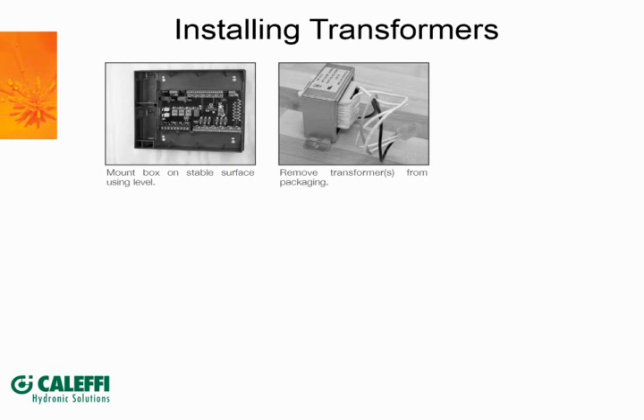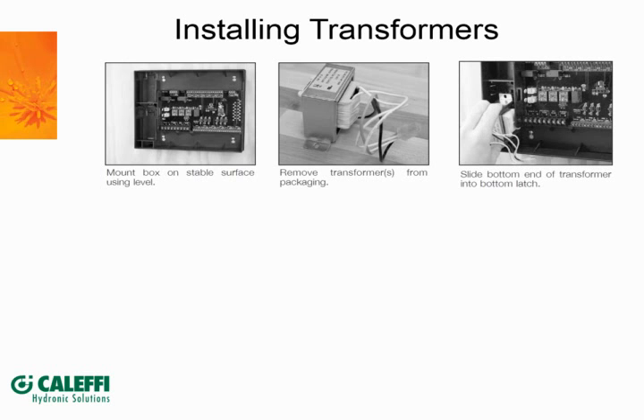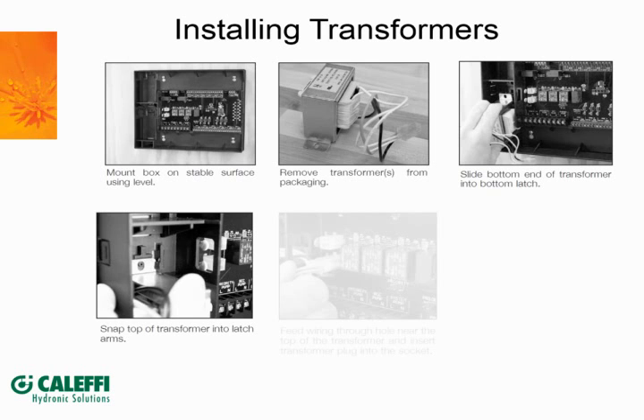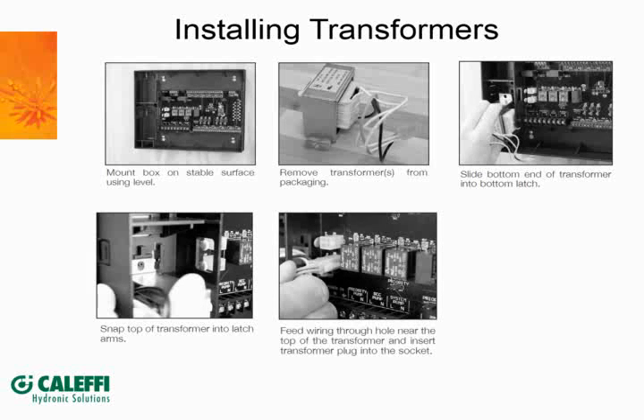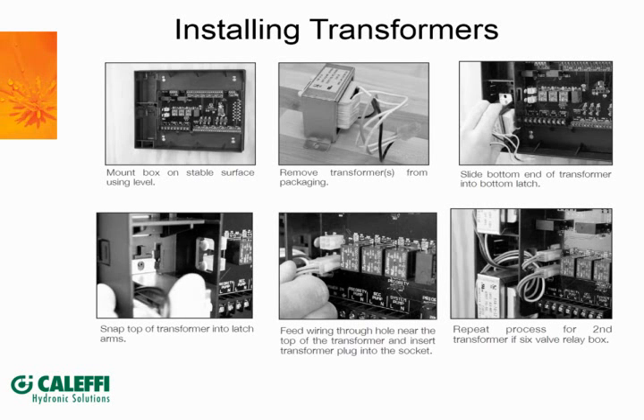So once you get it, you remove the cover, just like we showed with the other control, and then you take the transformers out of there. I don't show it real well, but there's a little bit of a slot right here. You tuck the transformer underneath that slot, and then it snaps in place with the arms up here. Once the transformer's in place, there's a simple plug. It can only be installed one way. Snap that plug in there, and you're good to go.